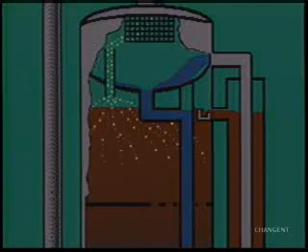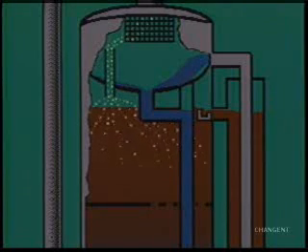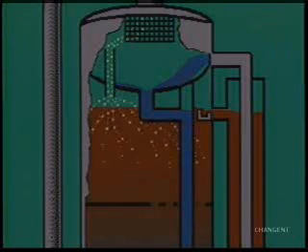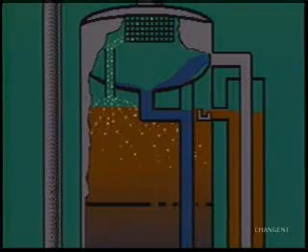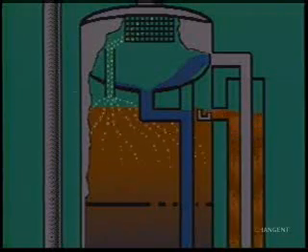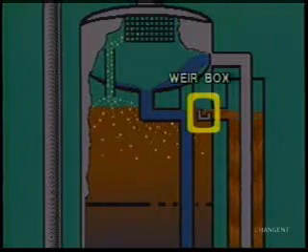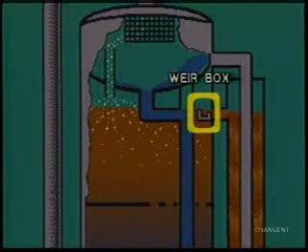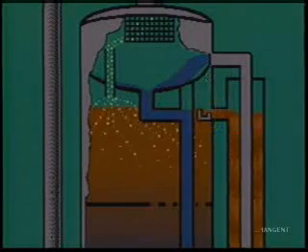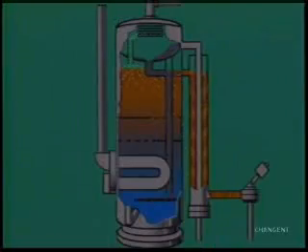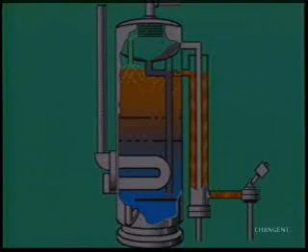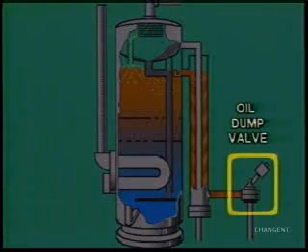Heat, chemicals, and gravity work together in the settling section, quickly breaking the emulsion. Finally, the clean oil flows out of the treater through a weir box — a dam-like structure which maintains liquids at a specified level. The oil flows down the outer shell of the heat exchanger, through the oil dump valve, and into a stock tank.